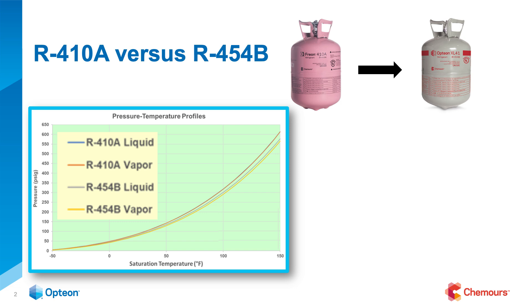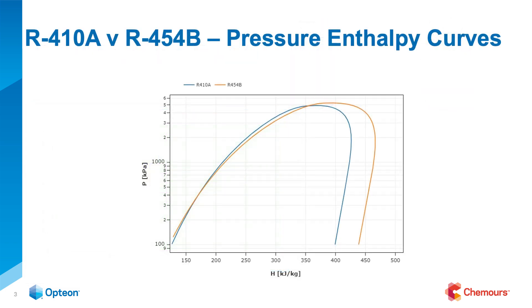Another thing engineers like to do is look at the pressure-enthalpy curves and see how closely they match in terms of pressures, net refrigeration effect, and those types of things. Again, you can see they're very, very similar. There's a little spacing on the right side, which basically means you get a little more net refrigeration effect, but some of that changes based on your system. You like to see this kind of agreement when you're getting a new refrigerant and want it to perform like an old one.